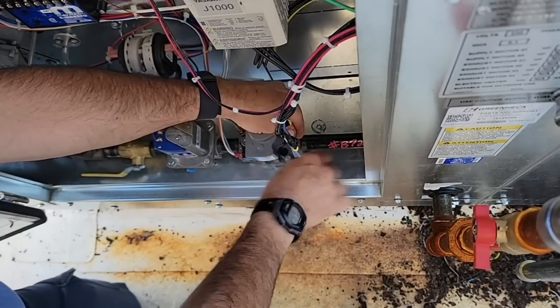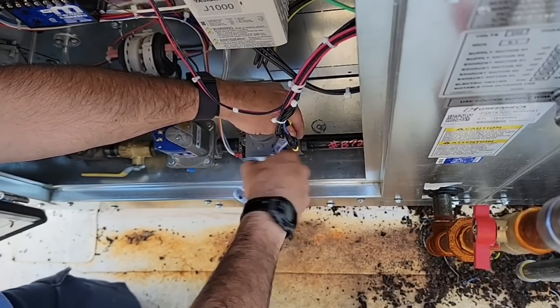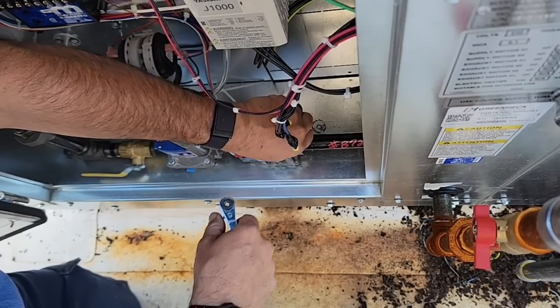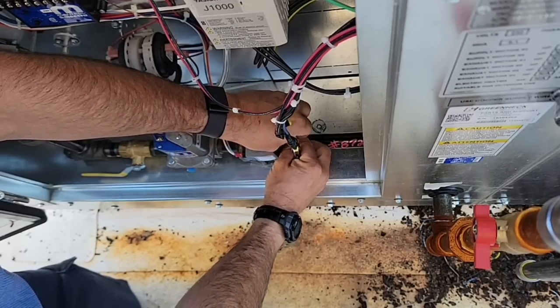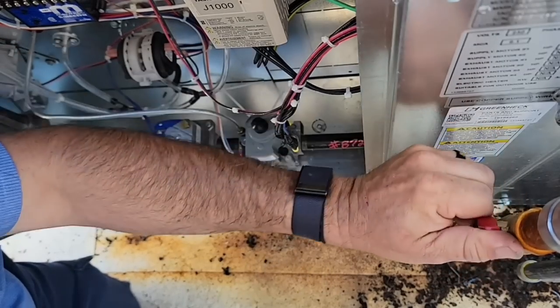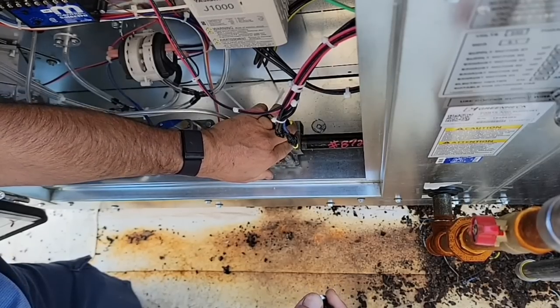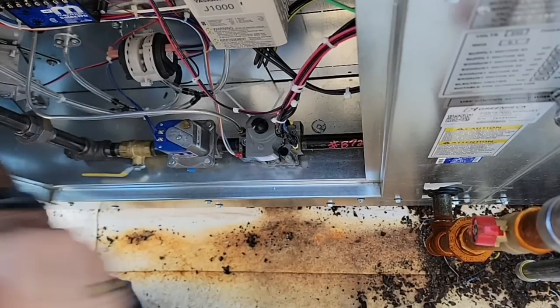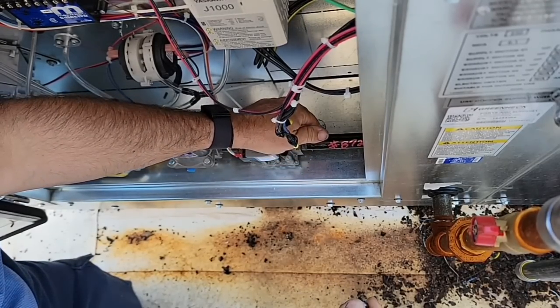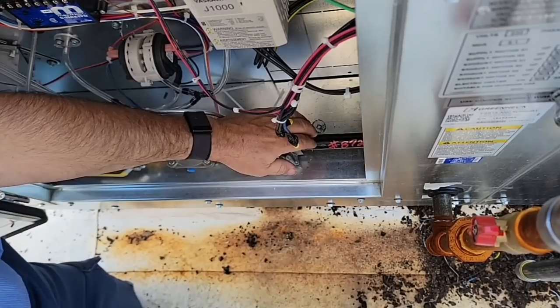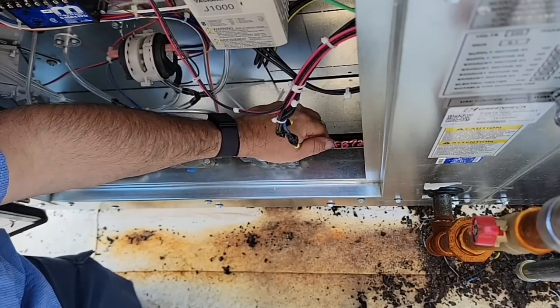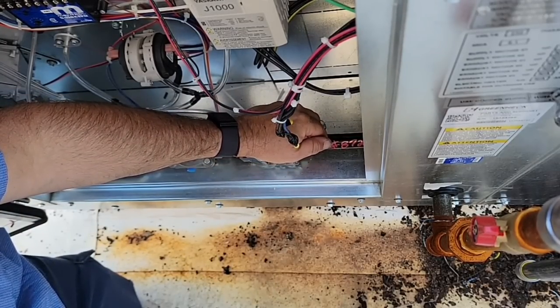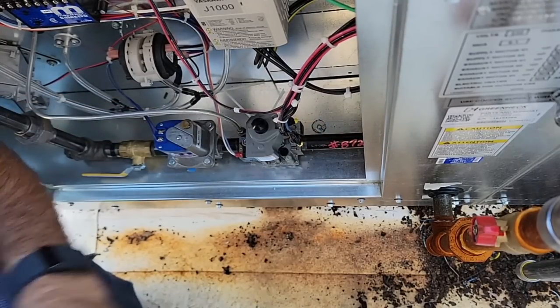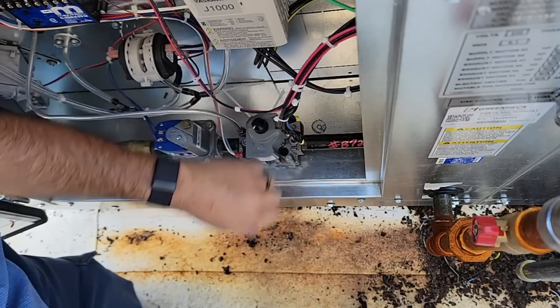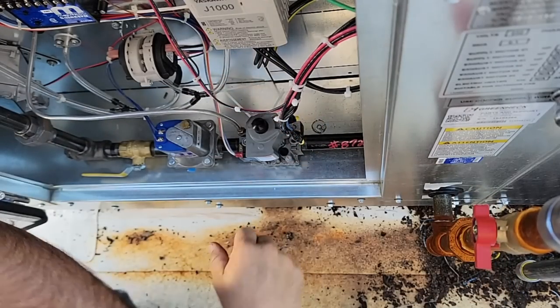All right, so we're gonna wanna check our gas pressure coming into the unit, make sure it's in our spec, which it should be, but this is all fairly new gas line, so we have gas coming. Probably gonna need to bleed for a while, so it's a good idea to go ahead and bleed it now. This would take forever if you just let it bleed on its own through the pilot mechanism. I think it's there. Okay, good. Now I'll go ahead and check our pressure.